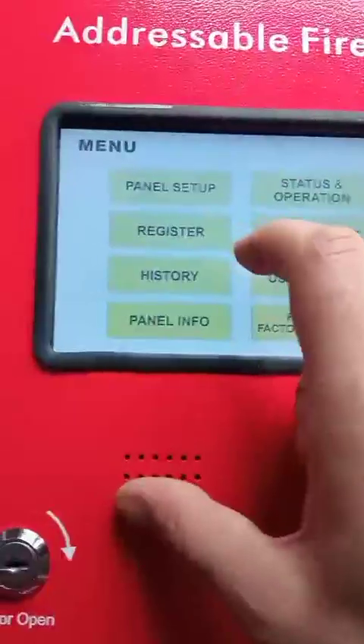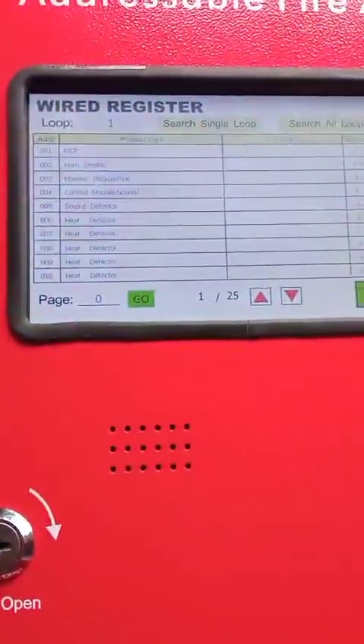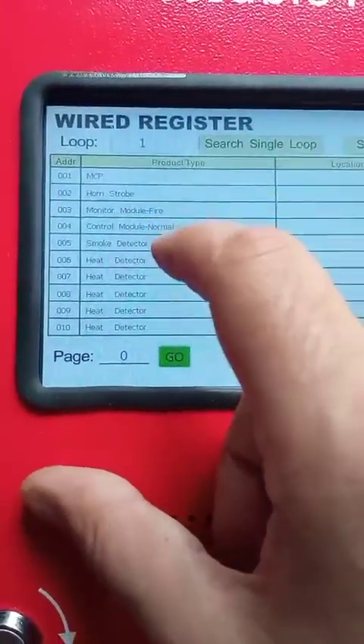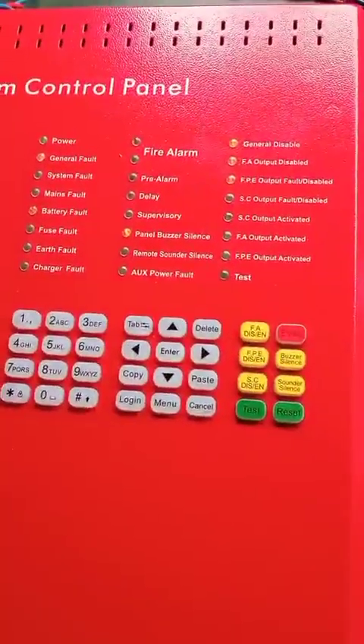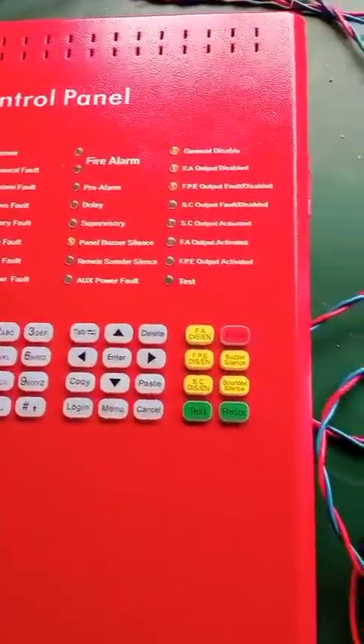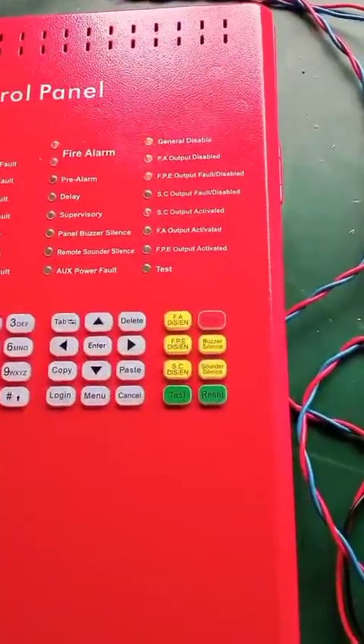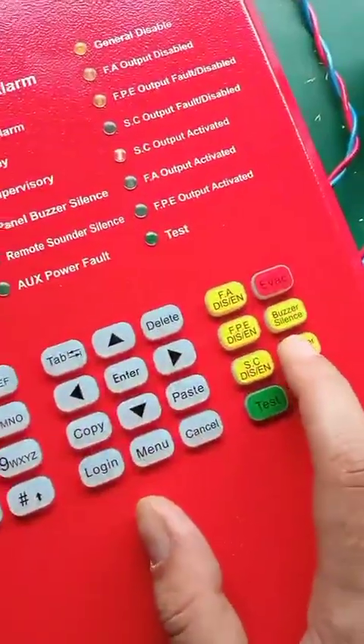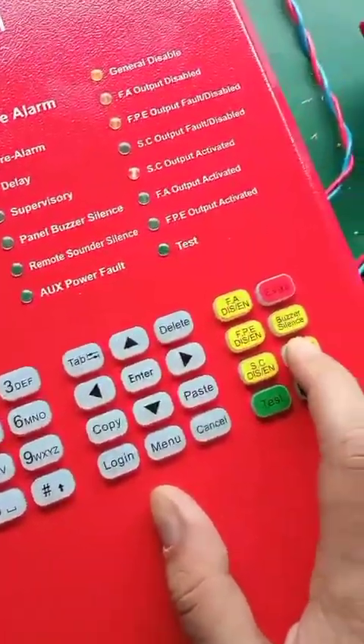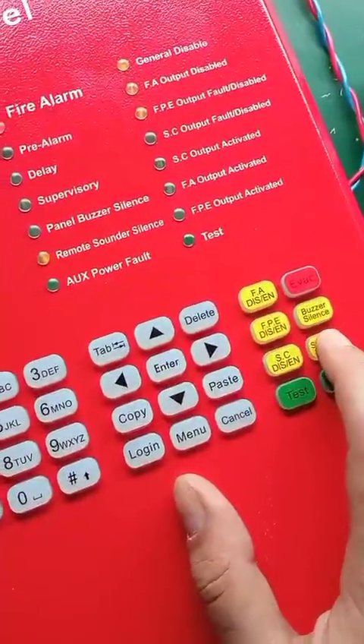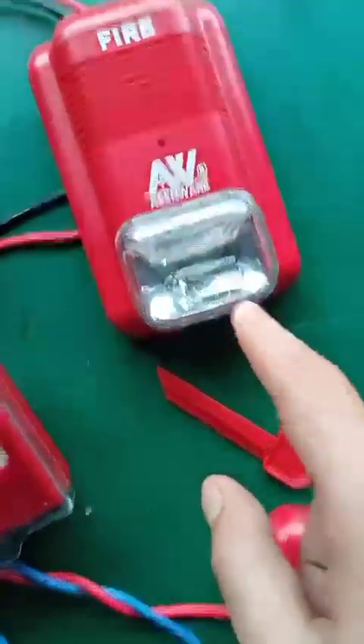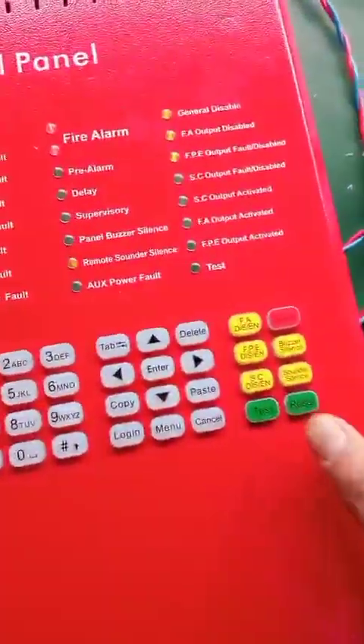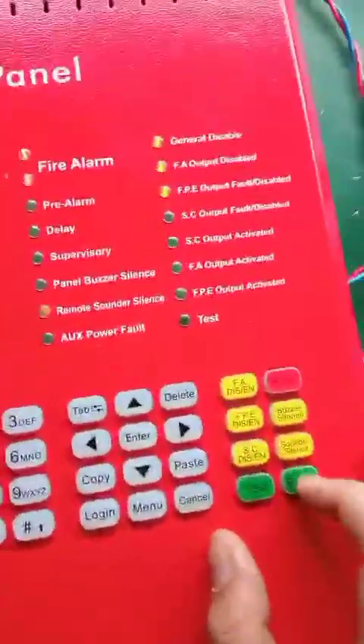Now I will show you the control module function. This control module is set to normal. So when there is a fire and I press the sounder silence button, you can see this stops working but this other sounder does not stop — even when I press silence it does not stop. I need to reset the panel because I chose fire mode.